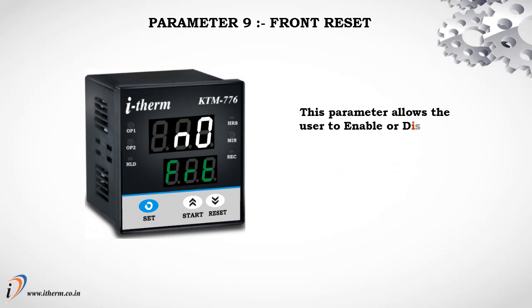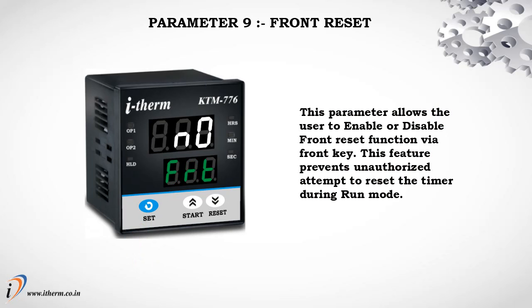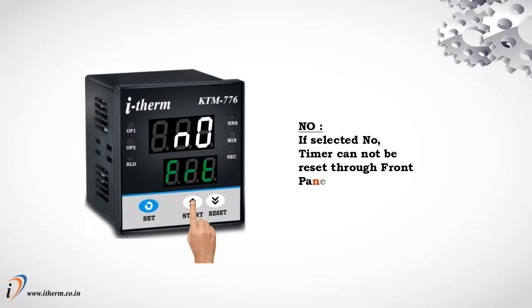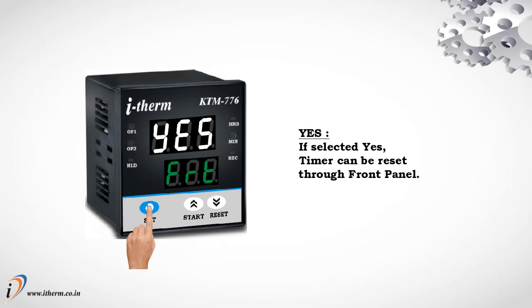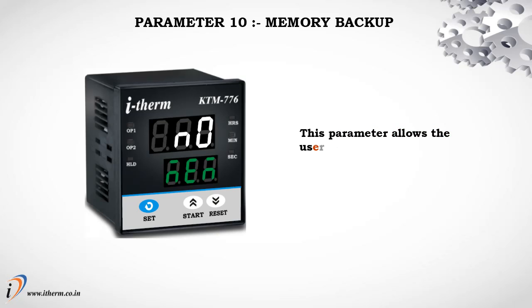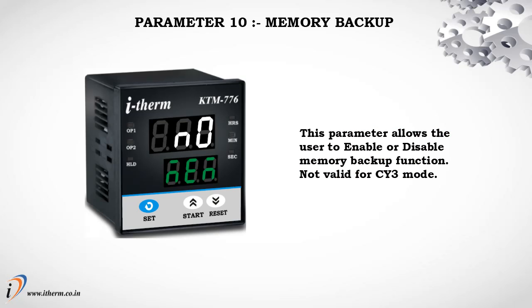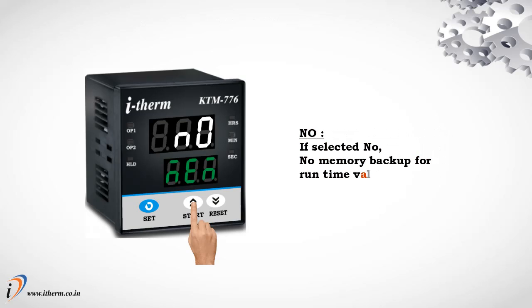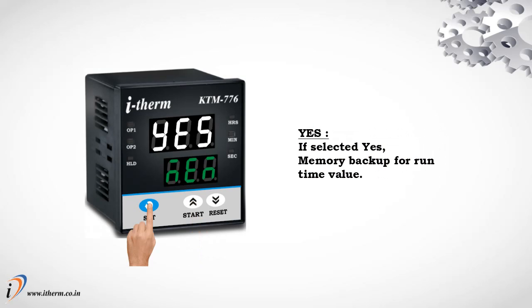Parameter 9: Front Reset. This parameter allows the user to enable or disable the Front Reset function via the front key. This feature prevents unauthorized attempts to reset the timer during Run Mode. If No is selected, the timer cannot be reset through the front panel. If Yes is selected, the timer can be reset through the front panel. Parameter 10: Memory Backup. This parameter allows the user to enable or disable Memory Backup. Not valid for Cycle 3 mode. If No, there is no memory backup for runtime value. If Yes, memory backup is enabled for runtime value.